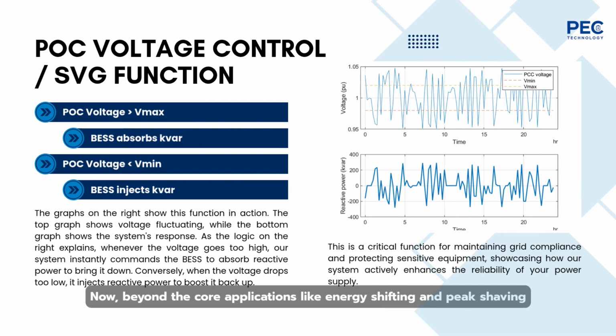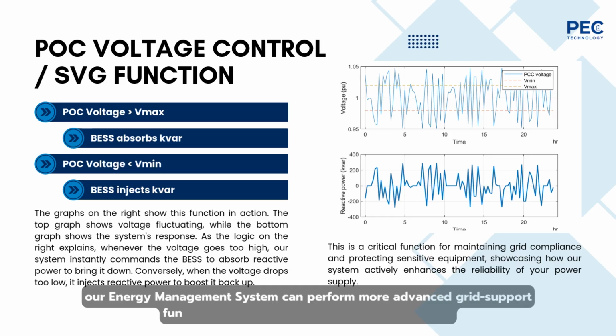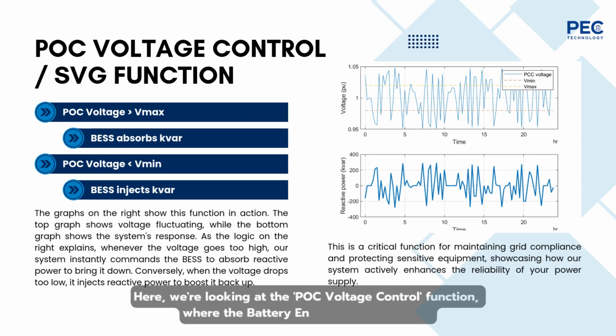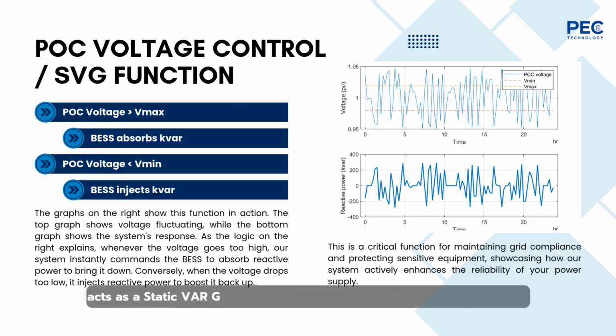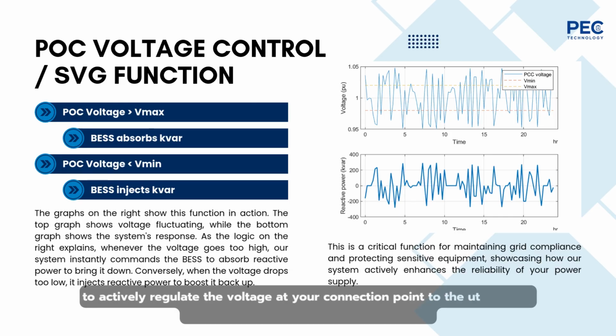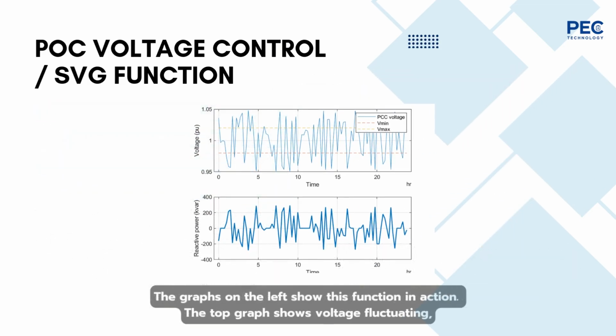Beyond the core applications like energy shifting and peak shaving, our energy management system can perform more advanced grid support functions, and this slide shows a prime example. Here we're looking at the POC voltage control function, where the battery energy storage system acts as a static VAR generator, or SVG. Essentially, we use the BESS to actively regulate the voltage at your connection point to the utility grid, ensuring high power quality and stability. The graphs on the left show this function in action.